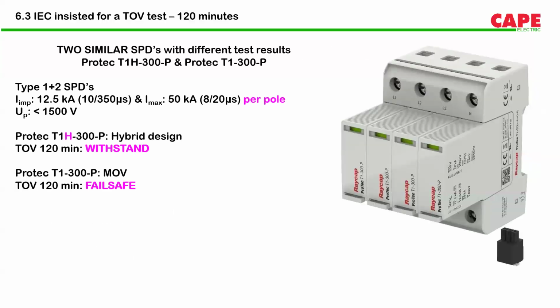These are the SPDs which come with TOV immunity. We have two different models. Just for example, I am showing this particular model. The first model is Protec T1H. The same model has now been upgraded to TSD T1H, which comes with a Cape brand. The basic difference between T1H and the T1 series SPD is that T1H has TOV immunity, that means it is tested with TOV 120 minutes withstand, whereas T1 is an SPD tested with TOV 120 minutes fail-safe.